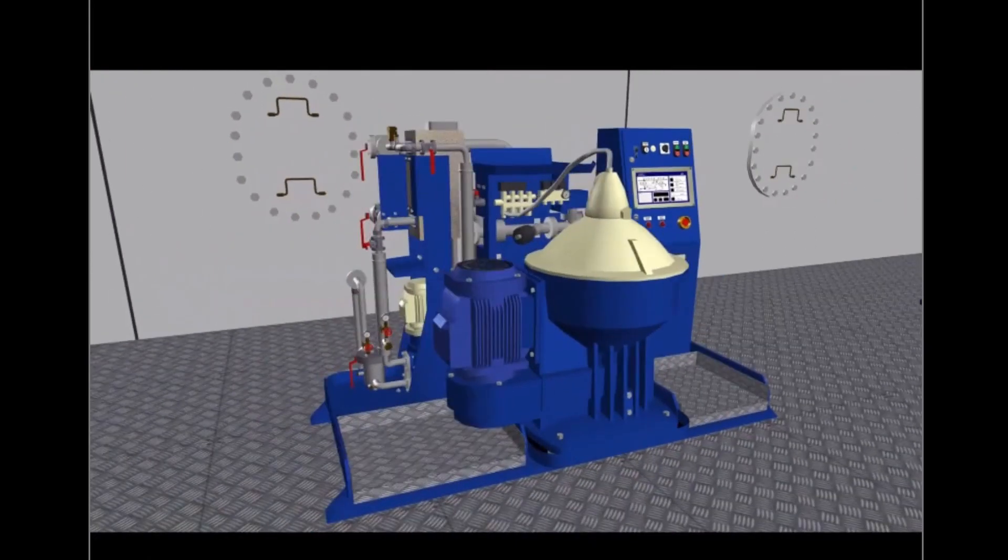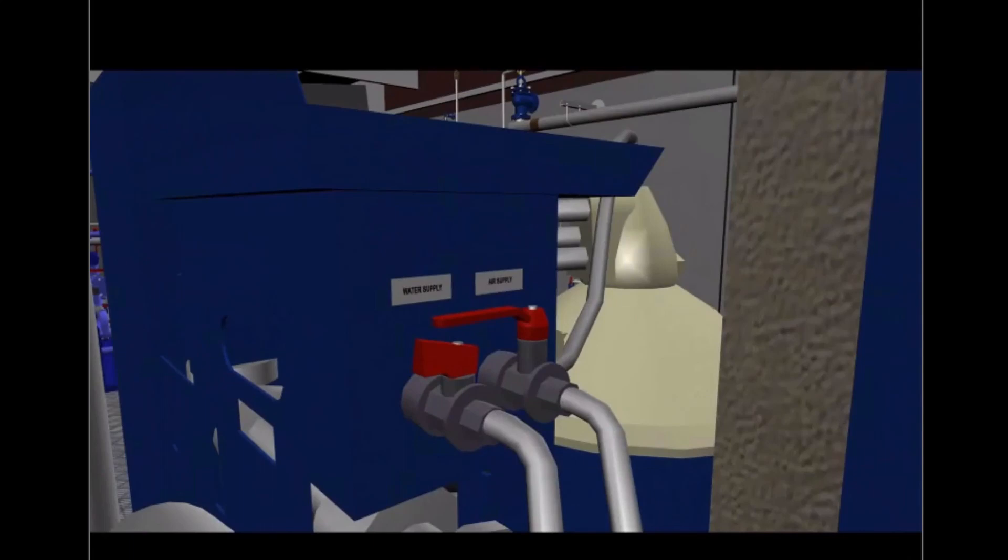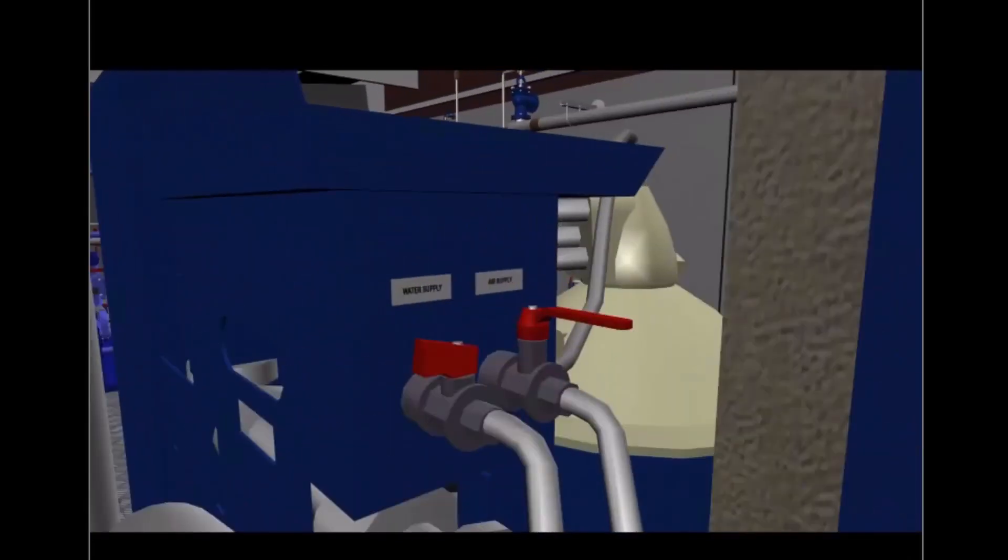Before start-up, make sure that the air supply to the air valve block is open and check that the air supply is correct. It should be between 5 and 7 bar, which is 0.5 to 0.7 MPa. Make sure that the water supply to the water valve block is open.